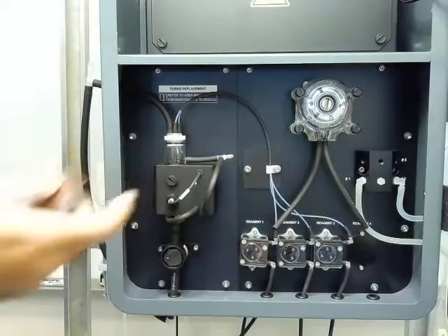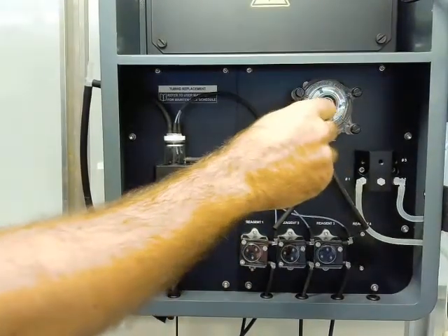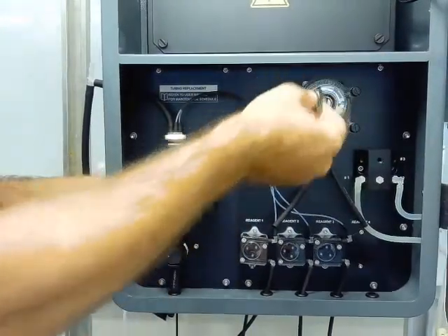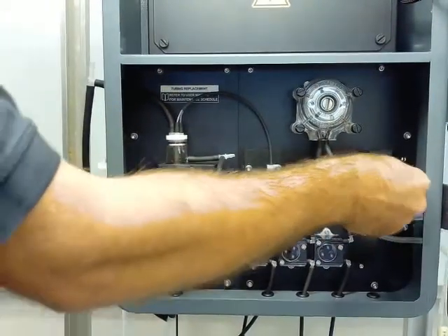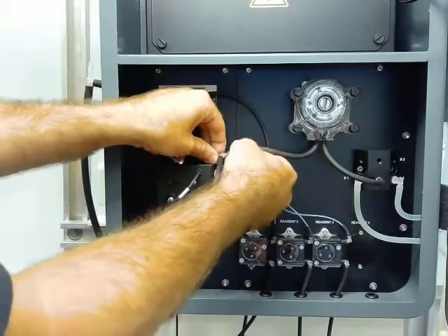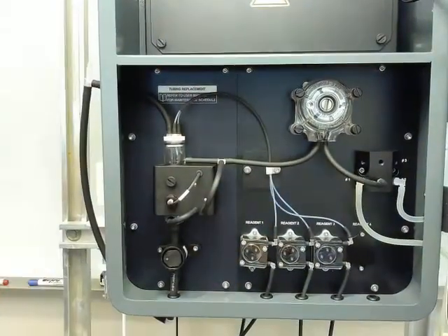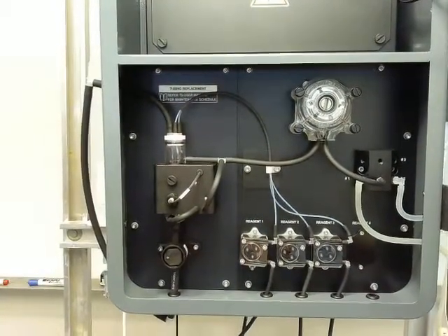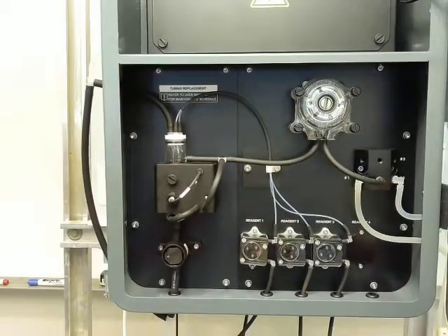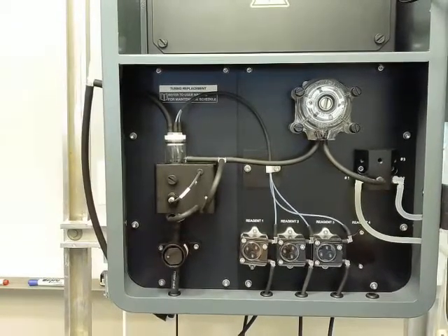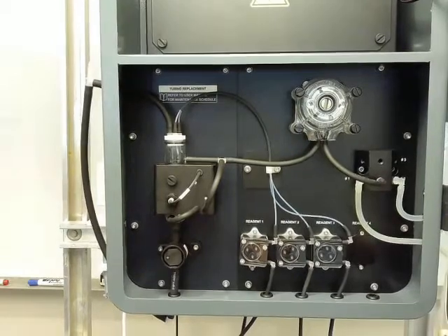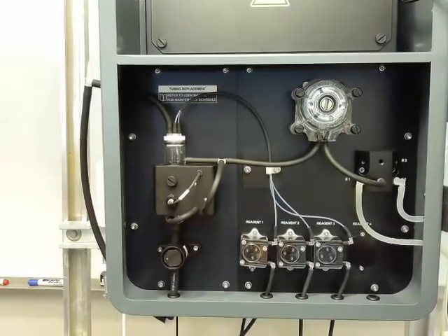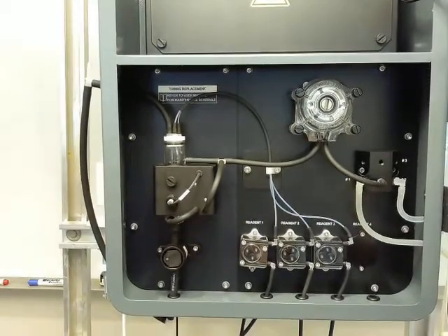Yeah, once these are finger tight, we don't have to tighten them too much. Finger tight, and then a quarter or a half turn or so is all you really need. And then just reconnect our tubing at both ends, and then that part would be complete. So at this point, I always like to do a check. Just run a manual command on our sample pump. Just draw in sample, make sure the tubing's in place properly, the pump's in place properly, and also double check that we did our drain tubing correctly as well.